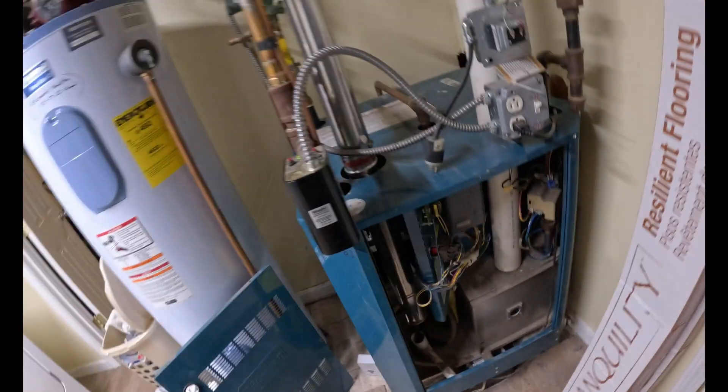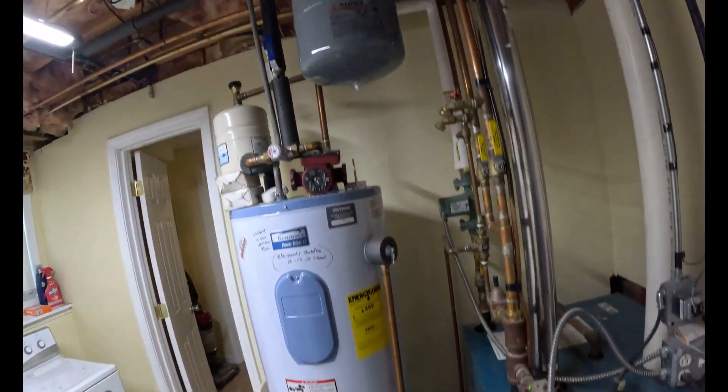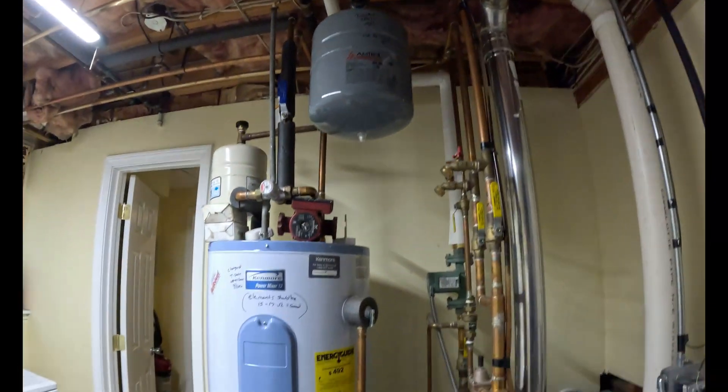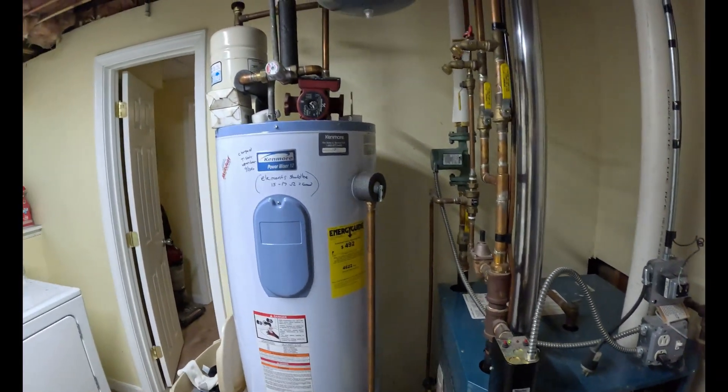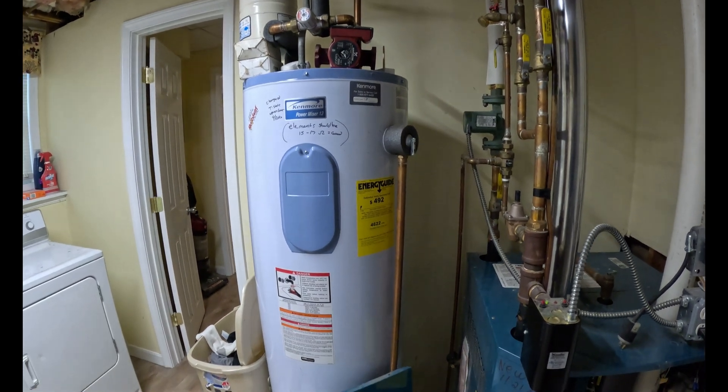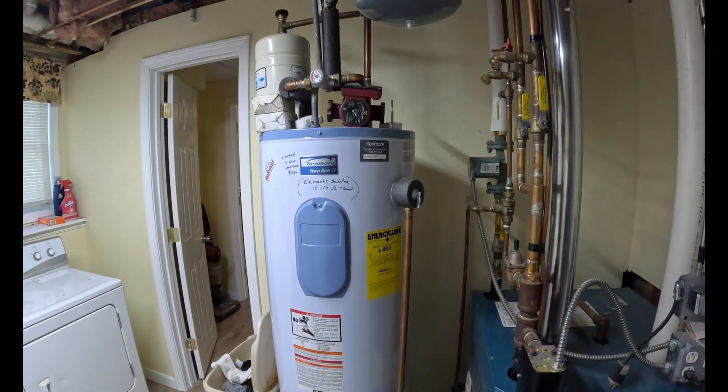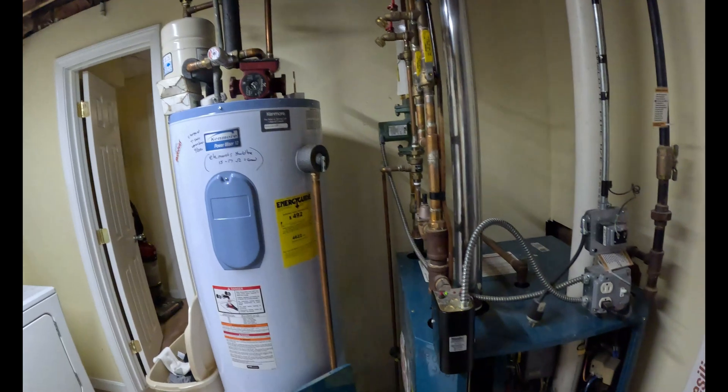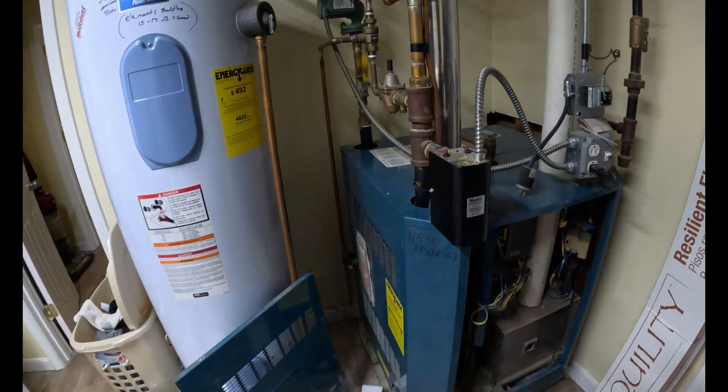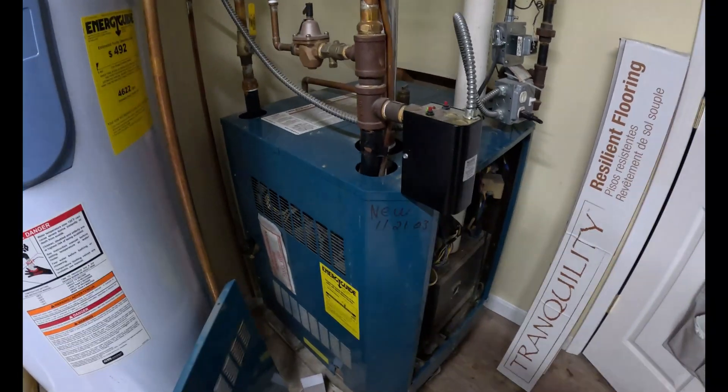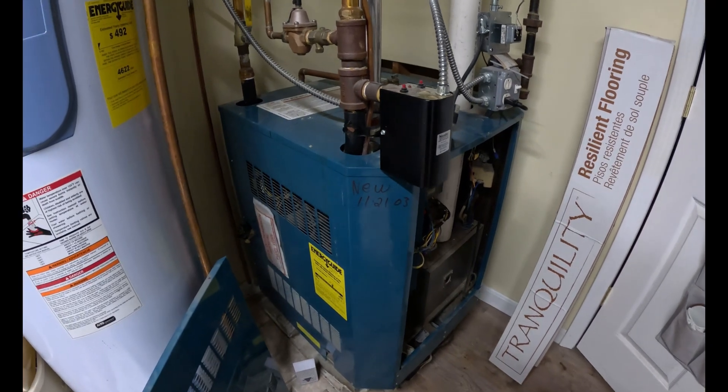If you wanted to add a Taco zone control board, you could do that pretty easily and run both these zones and then put an indirect. And currently this house has an electric water heater, which that may be getting changed to a heat pump water heater at some point. But this boiler was put in in 2003, she wants to keep running, so we're going to let her keep running.